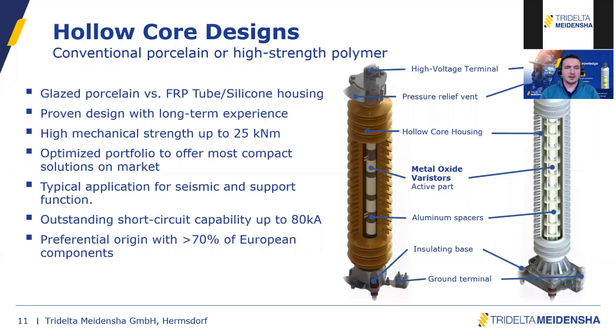They have higher mechanical strength. So depending on your requirements, typically if you have mechanical requirements, if you have seismic requirements, if there is some seismic activity in your countries, or if you have very specific short circuit capability, we would recommend using the tube design, the SBKT tube design on the right side. Of course, this is a polymer design. In some countries where polymer is still not largely accepted, the solution would be to use a porcelain solution. And maybe Philip will explain, during the short circuit part, the difference when you do a short circuit on a porcelain in comparison to a hollow core polymer.